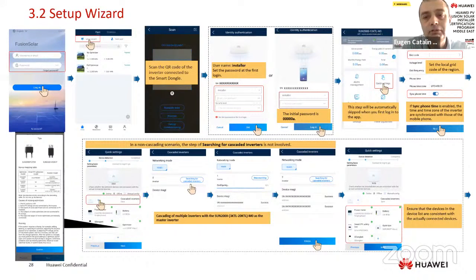And now we need to commission the inverter. What I need to do here is to log in to my account and choose the setup wizard. Of course, the inverter is on. Yes, it's working. The LEDs are green, no red, no fault. Okay. After that, we scan the QR code of the inverter.